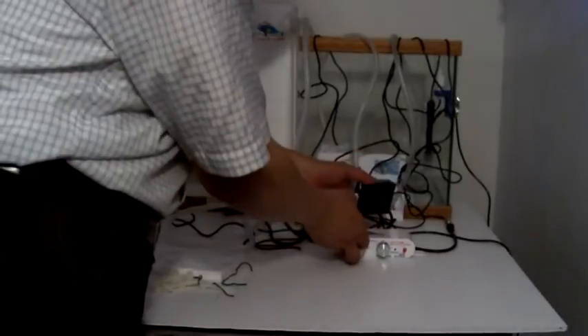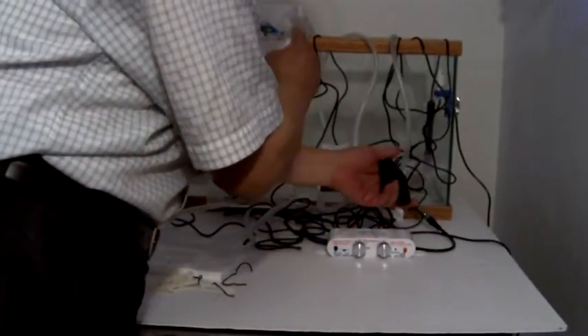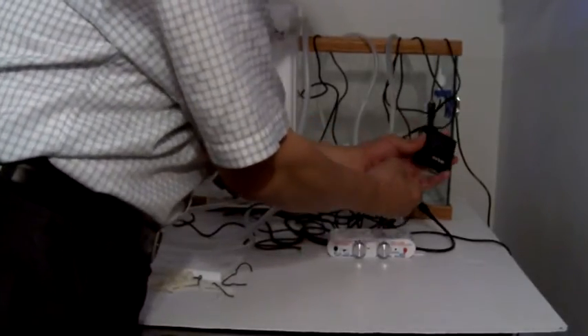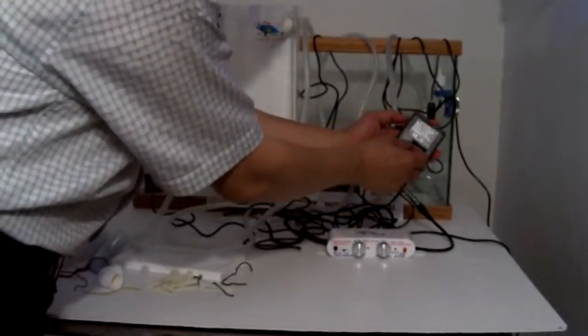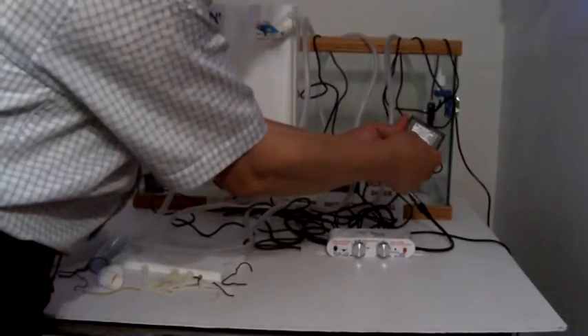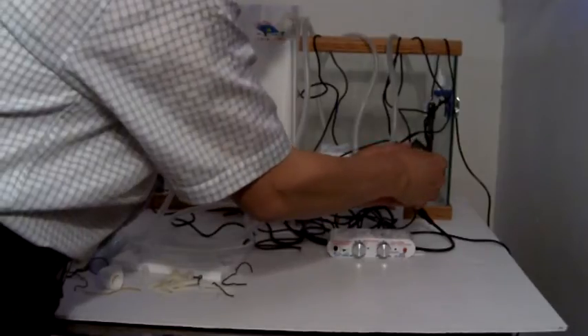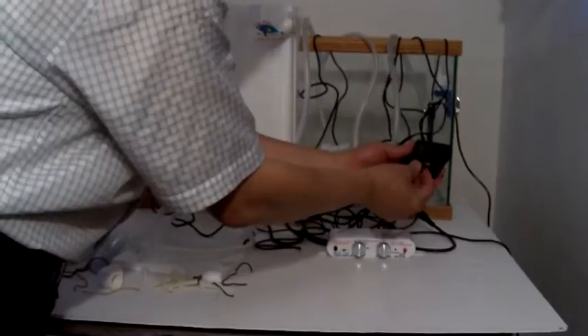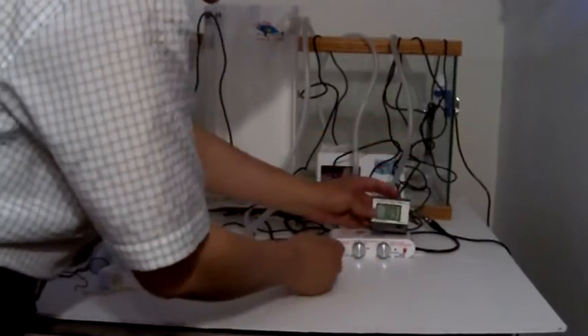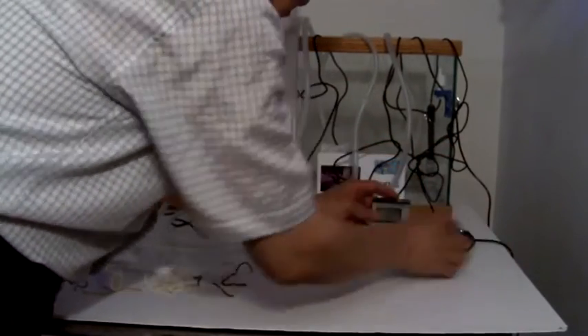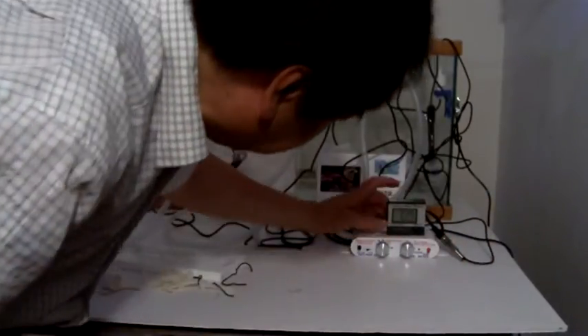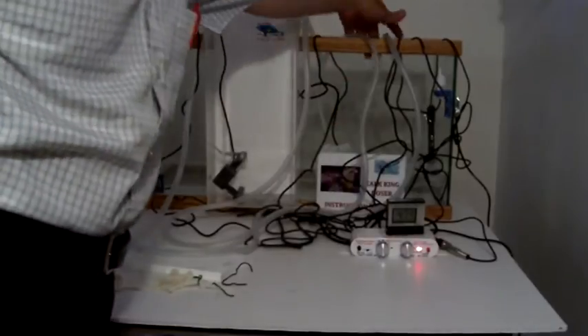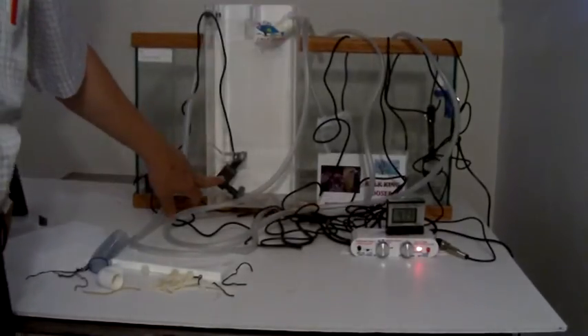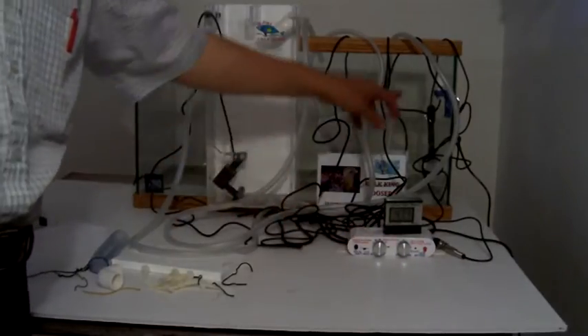Now it's time to power up the unit and do some functional checks that the computer will do for you. First, when the pH meter comes, the battery has a tape on it — you have to pull it out in order to use the battery, otherwise the battery is not consumed. Later on you can plug in an AC adapter if you want. Right now, since the power is not turned on, the reading is kind of meaningless. When I turn on the device, you'll hear the controller give a beep sound, then it will exercise the feed pump for 3 seconds and the bypass pump, then it beeps 2 times to say the flow switch is off.